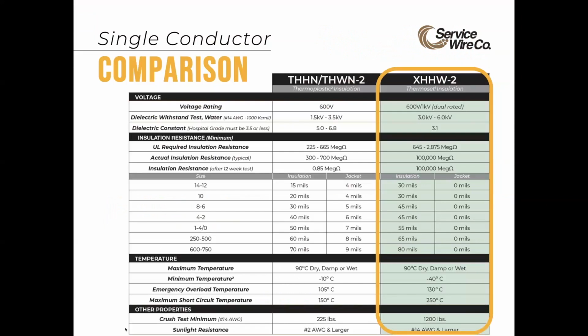Industrial end users only want thermoset XLPE cables like XHHW-2, USE-2, and RHW-2 because they're all made with cross-linked polyethylene instead of PVC and nylon. XLPE products like the XHHW-2 highlighted here are more resistant to chemicals and abrasions and far less toxic than PVC in the event of a fire or corona discharge.